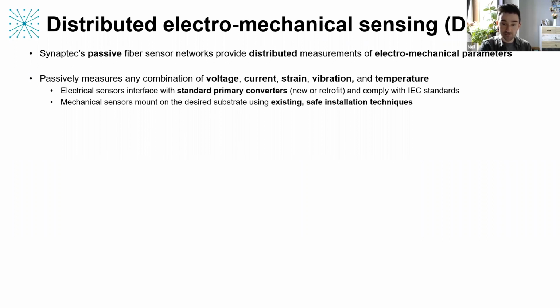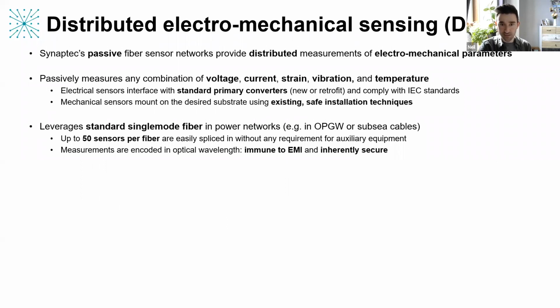If one of these point sensors is electrical, it will interface with the secondary side of a standard primary converter, so a current or a voltage transformer. And we can provide that primary connection, or we can retrofit to the secondary of an existing device. And those comply fully with the IEC standards of the industry. If it's a mechanical sensor, then that simply mounts onto the desired substrate to be measured for strain, vibration, or temperature. And that uses standard, existing, and safe installation techniques that would be familiar to any installer in the offshore industry. As I've said, we leverage the existing standard single mode fibre in that power network. So in the subsea sector, obviously that's the bundle of many fibres that you have in the cable itself. And with just one of these fibres, we can deploy up to 50 sensors for these parameters shown on the screen.